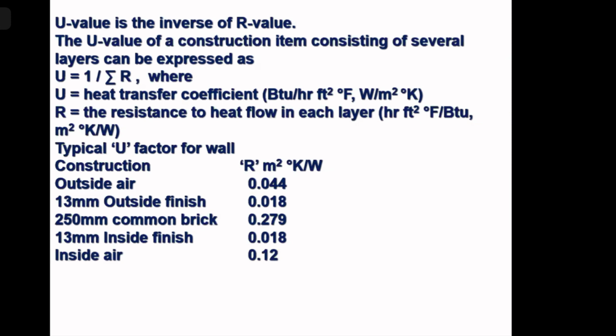You see, outside air R value is less than inside air. Why is it so? Outside air is turbulent because continuously there is wind flow. So a turbulent boundary layer has lesser resistance to heat. That means heat transfer is more in a turbulent boundary layer. That's why we have made the turbulent boundary layer for cooling coil fins. And inside air is reasonably still, calm and quiet, no air draft within the room, no storm, no outside air movement inside the room. So it provides a more or less laminar boundary layer, so it has more resistance.